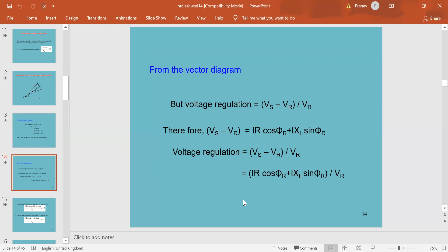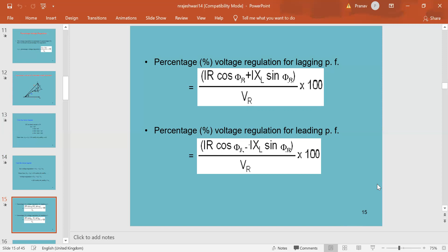And coming to the percentage voltage regulation, the percentage voltage regulation for lagging power factor will be IR cos phi r plus IXL sin phi r by VR into 100, and the percentage voltage regulation for leading power factor will be IR cos phi r minus IXL sin phi r divided by VR into 100. So these are the approximate formulas for percentage regulation with lagging and leading power factors.